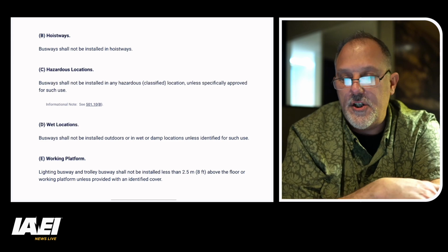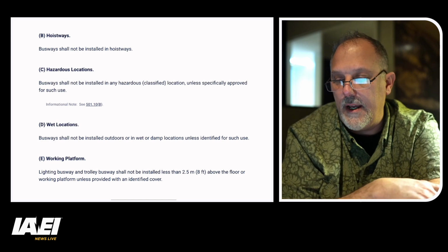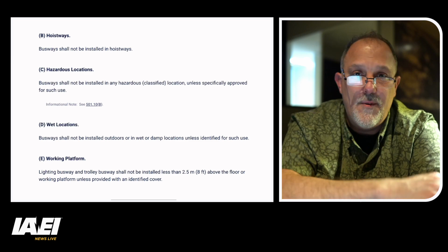If you put it in a wet location, and I honestly am not even sure why, when I look at D in this list, it says busways shall not be installed outdoors or in wet or damp locations unless identified for such use. Well, I could say that about any location that you're going to install equipment. It just, if you're using it in accordance with its listing, Mark, so I'm okay with the language there, because it's not technically inaccurate. It's a shame that we need it.